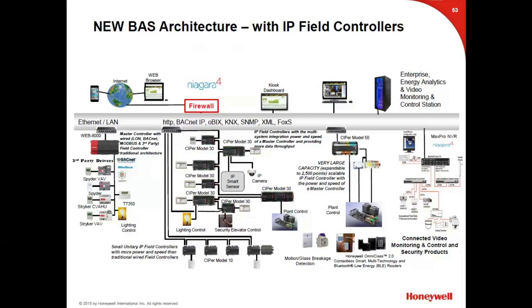That means if you have a program running on a critical environment air handling unit — an OR, for example — and you need to make a program change, you can connect to the network, get into that controller, and make a program modification while the unit continues running. When the change is done, it's live and active. There's no download step where the processor stops and loads a new program, shutting down your equipment. That is a pretty big feature. The last product, the CIPer Model 30, is about to be released in June.